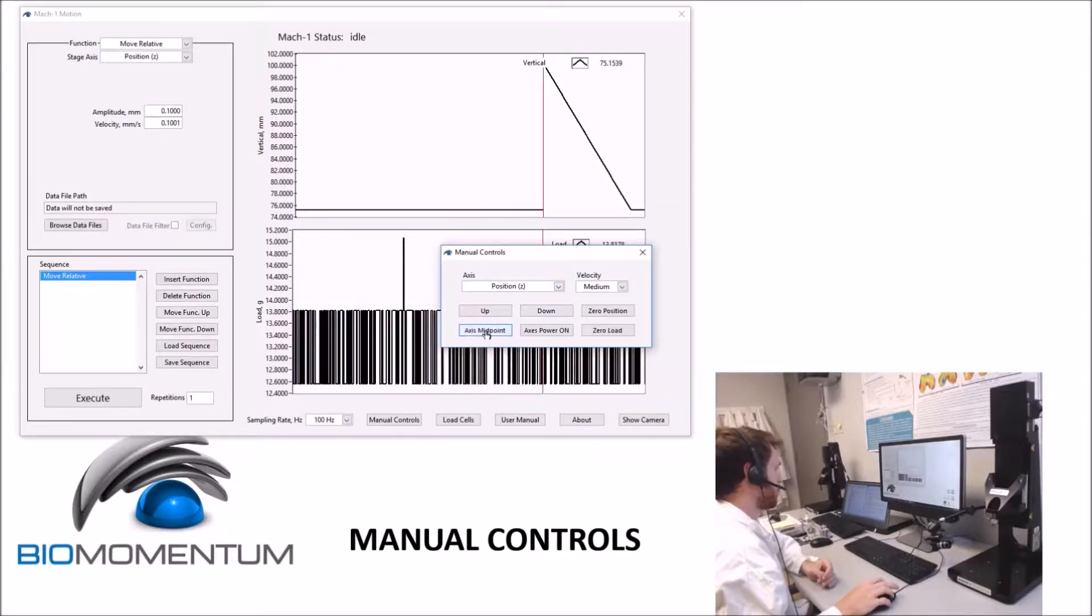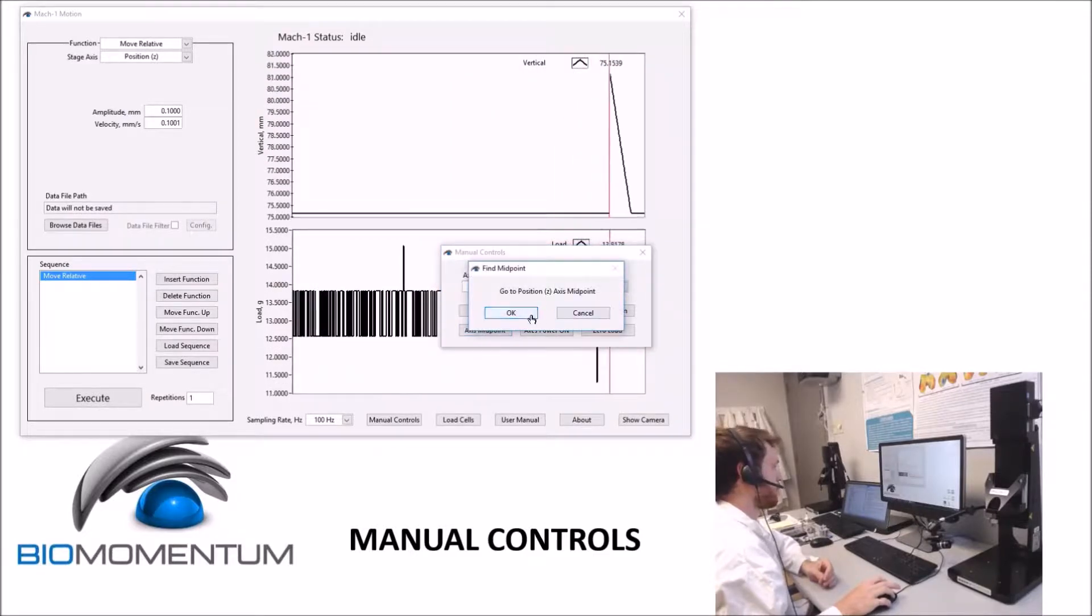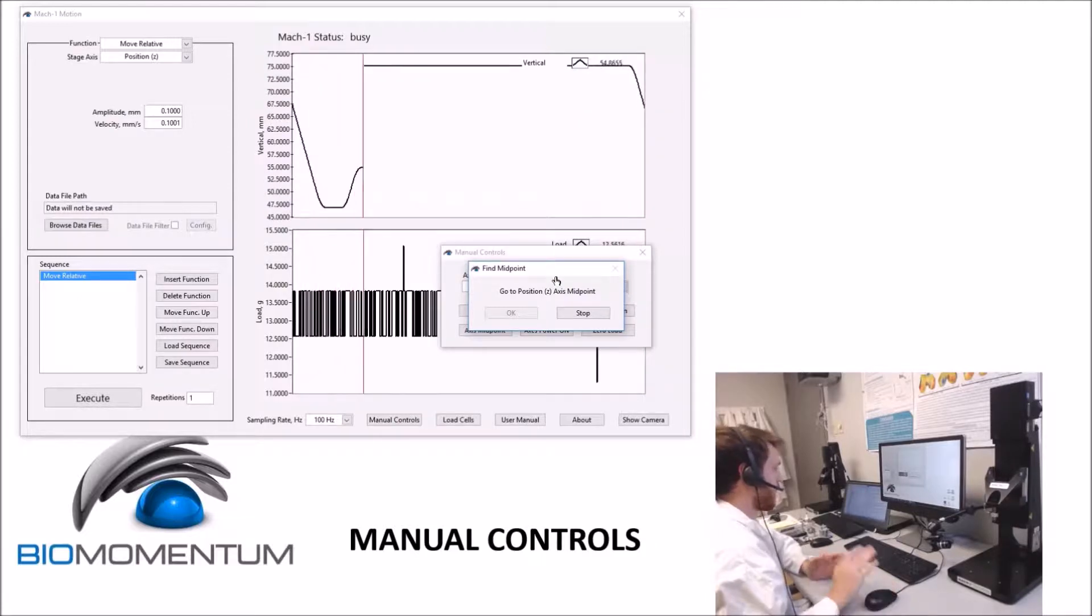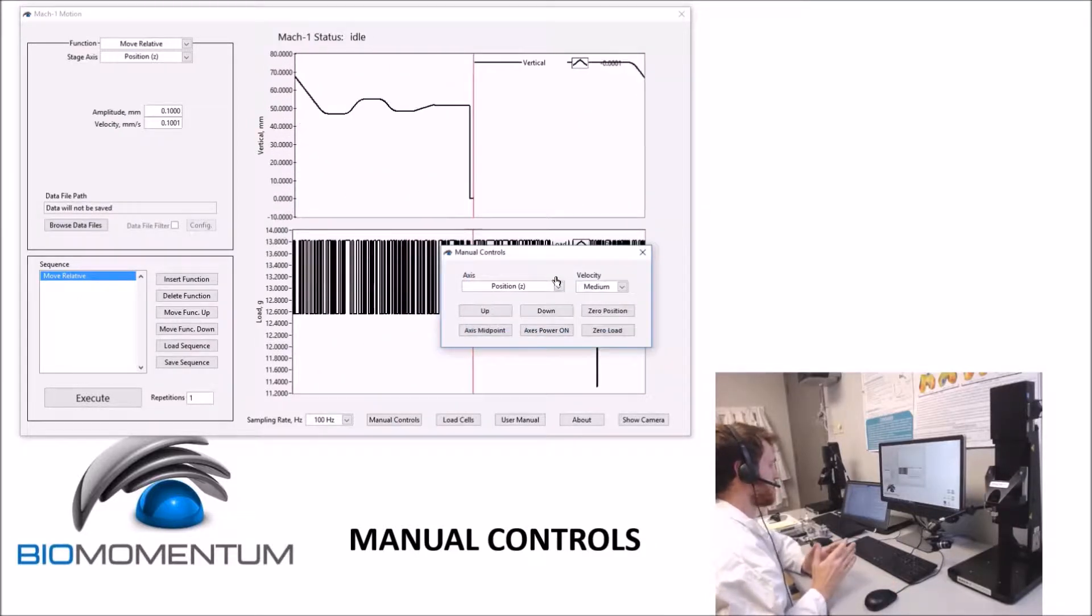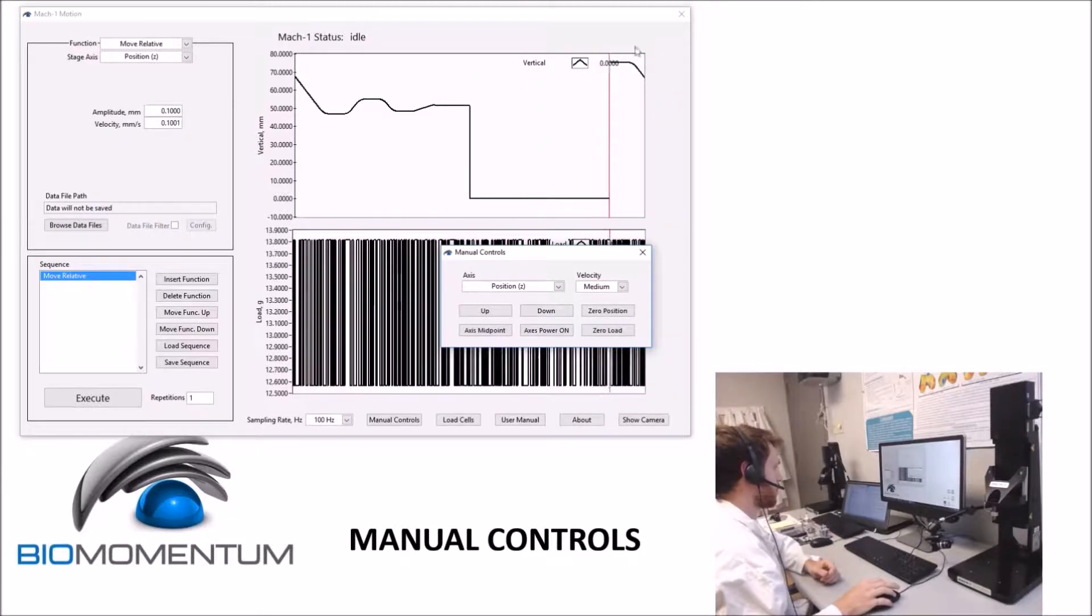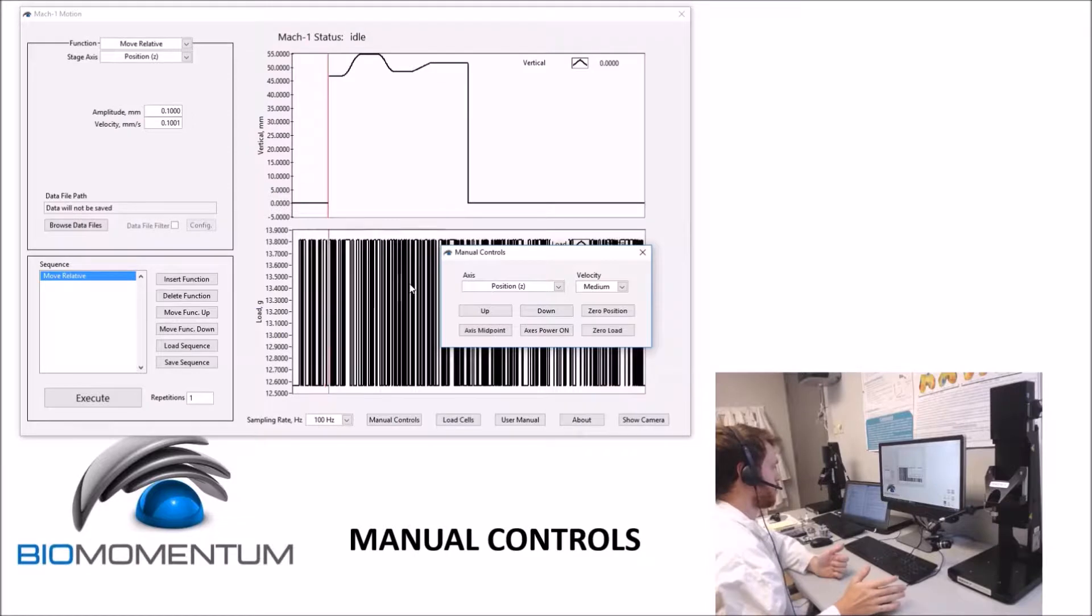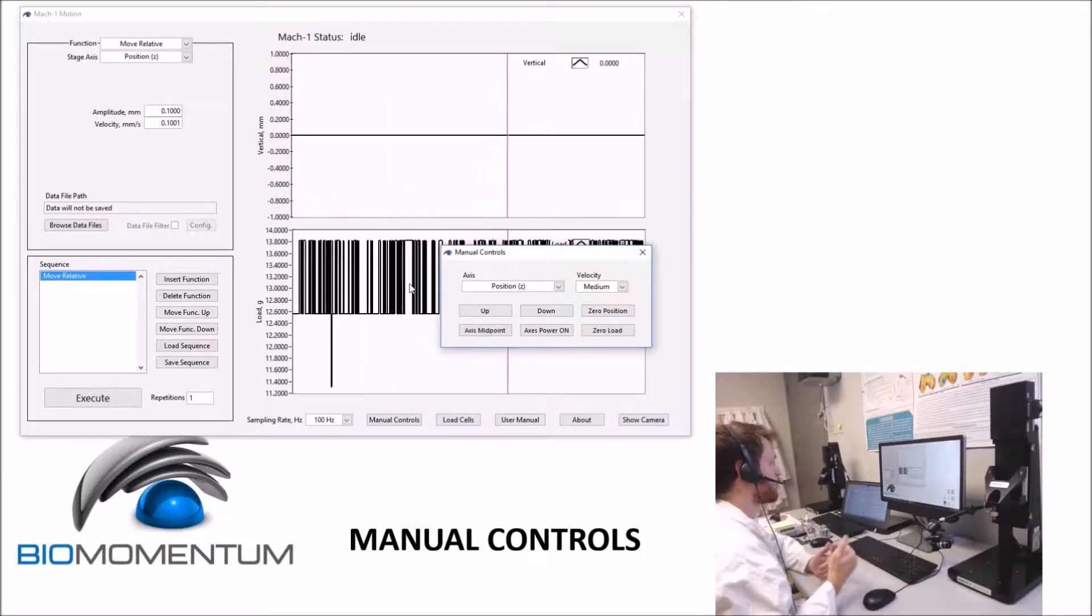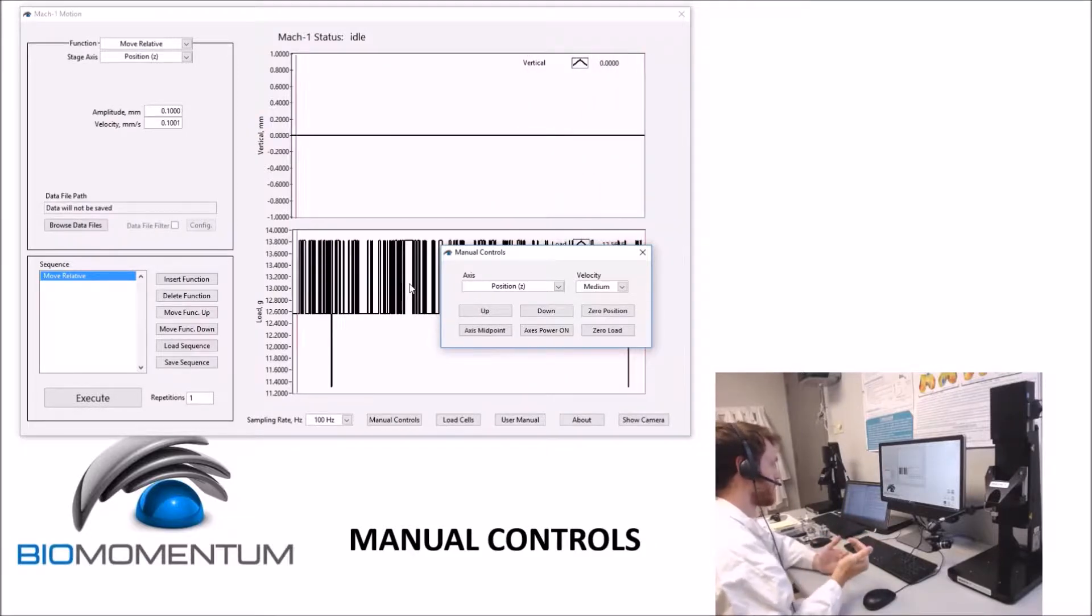Clicking the Axis Midpoint button will find the midpoint of the selected axis. The midpoint is an absolute reference. Upon reaching the midpoint, the motion controller will set the position to zero. Before choosing the Axis Midpoint command, make sure that the selected stage is always completely free to move along the displacement range. This is to make sure that the action will not overload the load cell accidentally.